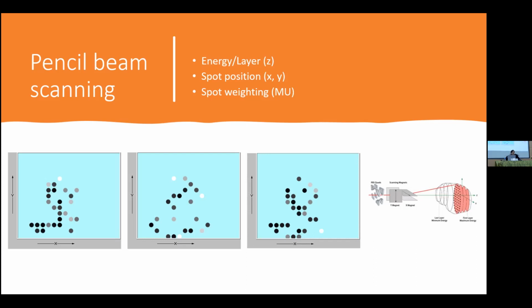And also the dynamic range. So at the end of the day, when you're doing these tests, what you're really testing in the nozzle, there's dose monitors and spot position monitors, things to make sure that the vendor has to make sure the system is operating correctly. And what you're really testing is to make sure those are operating right. Because if those are operating correctly, if something goes wrong, there's going to throw a beam abort. If the beam is going to the wrong place, the system should prevent that from happening. At the end, anything it should detect is not going to the right place and stop. So you have to have equipment that is able to properly test those things and know how to test those, what we call interlocks, to make sure that that system will actually stop if something was to go wrong.